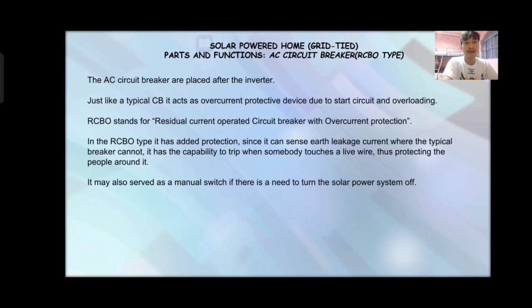So, RCBO stands for residual current operated circuit breaker with overcurrent protection. So, paano nga ba nagpa-function si RCBO? So, in the RCBO type, it has added protection. Since it can sense earth leakage current where the typical breaker cannot, it has the capability to trip when somebody touches a live wire, thus protecting the people around it. So, yun nga, yung added protection nga niya ni RCBO is once na mahawakan mo yung live wire, mag-auto trip na siya. So, walang masisirang system sa solar power system natin. So, napaka-safe gamitin ni RCBO kumpara sa circuit breaker lang.